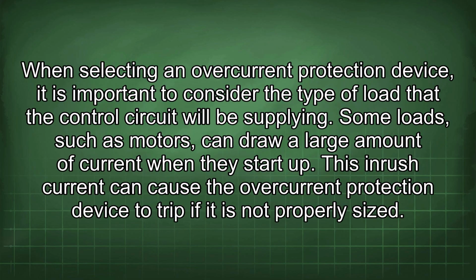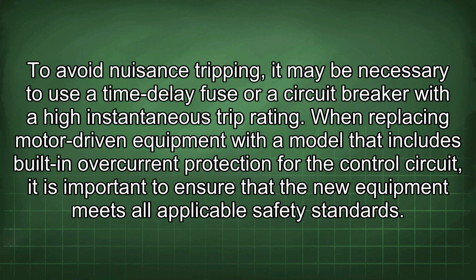When selecting an overcurrent protection device, it is important to consider the type of load that the control circuit will be supplying. Some loads, such as motors, can draw a large amount of current when they start up. This inrush current can cause the overcurrent protection device to trip if it is not properly sized. To avoid nuisance tripping, it may be necessary to use a time delay fuse or a circuit breaker with a high instantaneous trip rating.